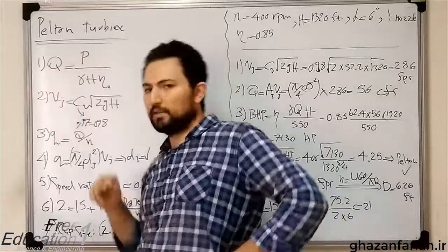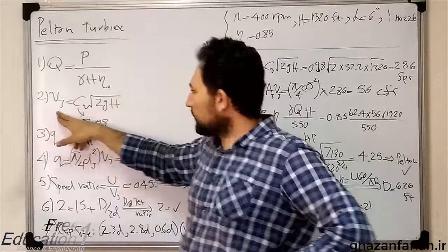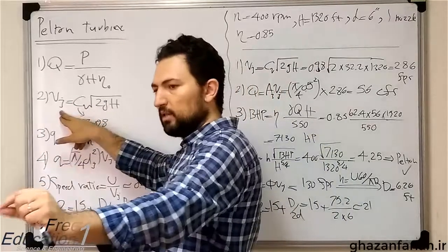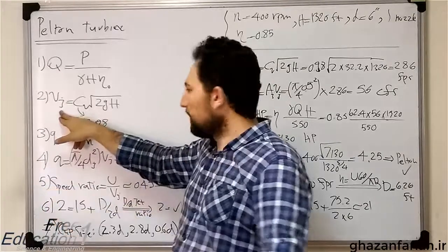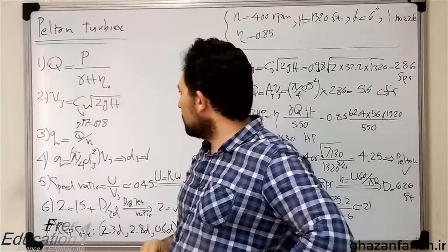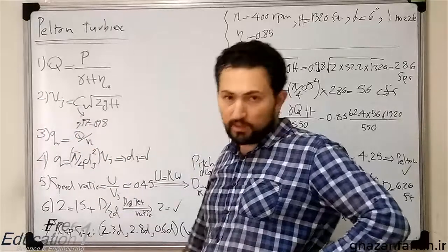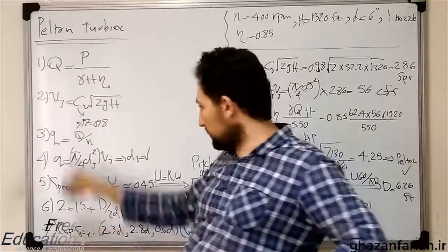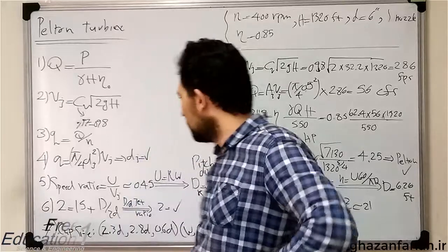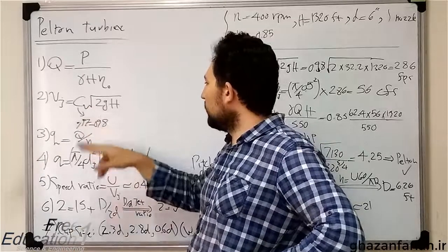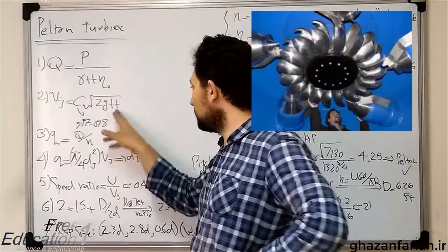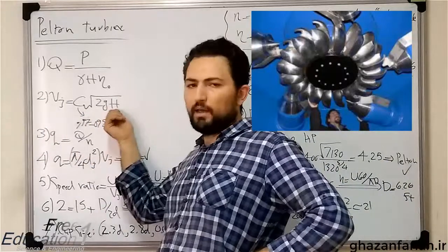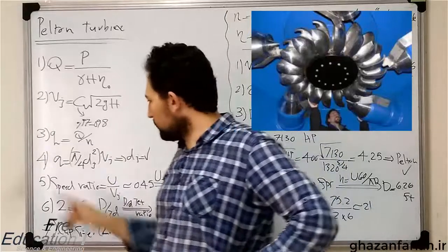The second step is a relation about the velocity of the jet, which leaves the injector and hits or touches the cup. The velocity of the jet is equal to a constant, velocity constant for example, which this constant has a magnitude between 0.95 to 0.98, and the square root of twice the gravity acceleration and the heads. This way, you can compute the velocity of the jet based on the head of the turbine.